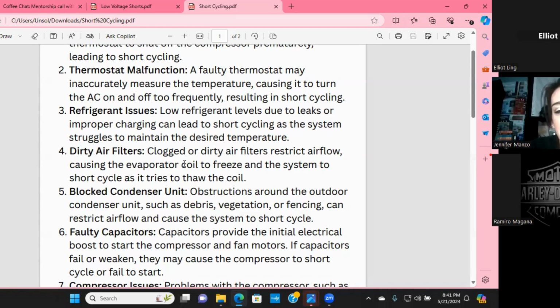Dirty air filters. This is a big one, you guys. And this goes for the next couple. Any dirtiness should not be there. And for the longest time, people just said, oh, it's run like that all year, it's fine. That is not true. It's not fine. It's slugging the compressor. It is possibly causing leaks from corrosion. Never, ever, if you guys show up even at a service call, say you're there to fix something and the problem isn't necessarily the dirty coil that's wearing a fur coat, but you notice the dirty coil wearing a fur coat, either take care of it right then and there with the customer's permission or ask the customer to schedule a return visit because they are not supposed to run like that.